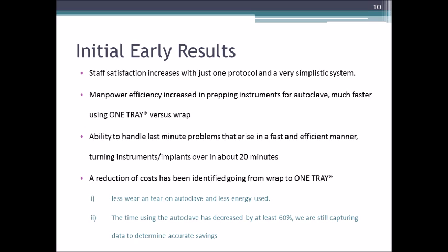The manpower efficiency increased in prepping instruments for the autoclave. It's much faster using the one tray versus wrapping them. Like I said, especially when we would get the 25-pan drop-offs. The ability to handle last-minute problems that arise. We still have folks drop things, or one-of-a-kinds hit the floor. Very fast turnover, so that turning instruments and implants over in about 20 minutes, which is just how long it takes the autoclave to go through the exposure phase. A reduction of costs has been identified, going from wrap to the one tray.